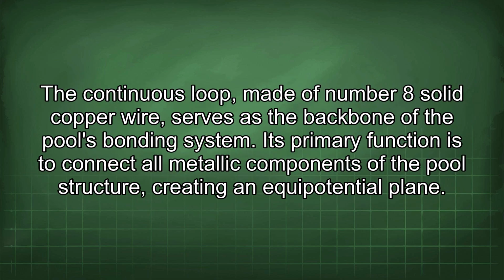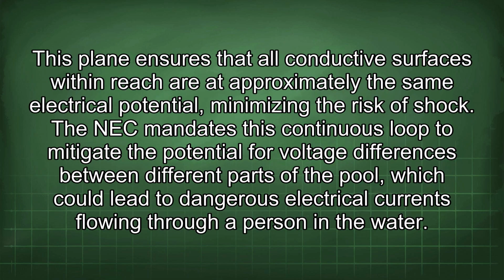The continuous loop, made of number 8 solid copper wire, serves as the backbone of the pool's bonding system. Its primary function is to connect all metallic components of the pool structure, creating an equipotential plane. This plane ensures that all conductive surfaces within reach are at approximately the same electrical potential, minimizing the risk of shock. The NEC mandates this continuous loop to mitigate the potential for voltage differences between different parts of the pool, which could lead to dangerous electrical currents flowing through a person in the water.